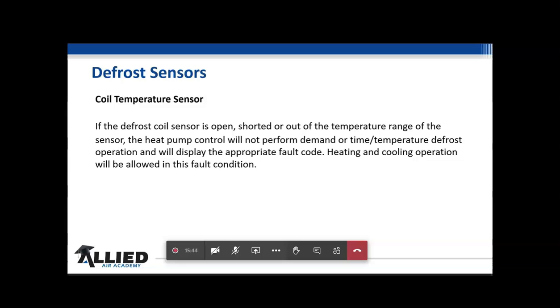If the coil temperature sensor goes out, if the defrost coil sensor is open, shorted, or out of the temperature range, the heat pump control will not perform demand or time and temp. It won't perform either one of them on defrost operation. It will display the appropriate fault code though. Heating and cooling will be allowed in this fault condition. So you're going to build up ice on this thing pretty bad.